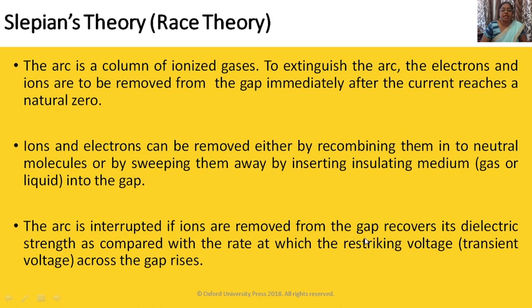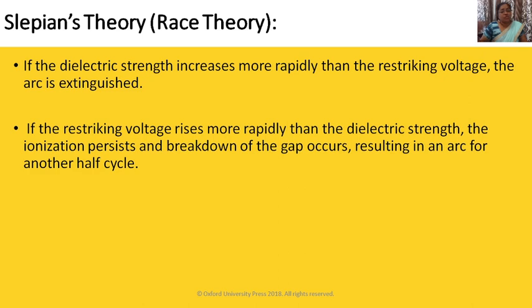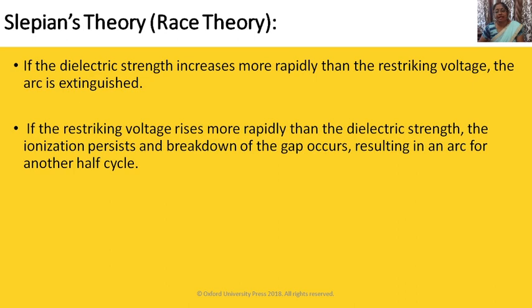If the ions are removed from the gap, it recovers dielectric strength compared to the rate at which the restriking transient voltage across the gap rises. If the dielectric strength increases more rapidly than the restriking voltage, the arc is extinguished. If the restriking voltage rises more rapidly than the dielectric strength — noting that different insulating media like air, vacuum, and SF6 have different dielectric strengths — the ionization persists and breakdown of the gap occurs, resulting in an arc for another half cycle.